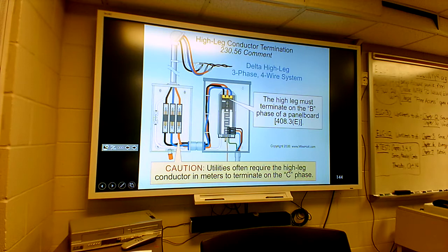Now, strangely, it's not strange, but on your service equipment, where it comes in from the power company, the high leg has to be on the third leg out there in the yard. The reason for that is whenever the meter base plugs in, it keeps up with your kilowatt hours. The meter base uses the first two phases, the A and the B, the L1 and the L2 phase, to actually power the meter base. Therefore, the high leg has to be on the third one, because the meter base itself uses the first two.